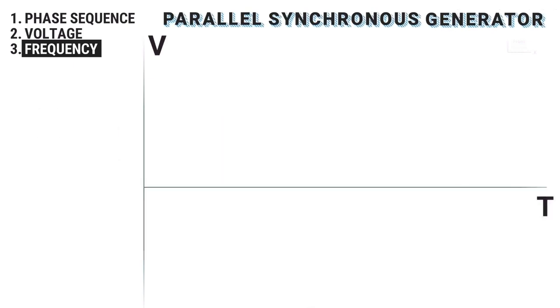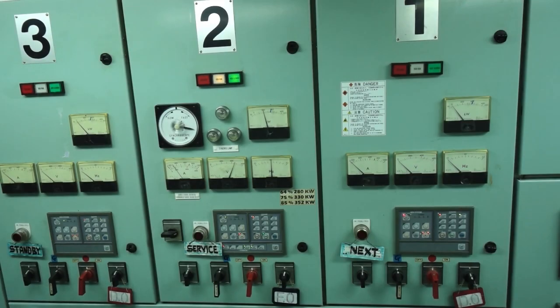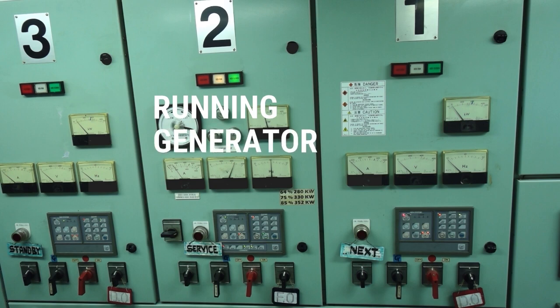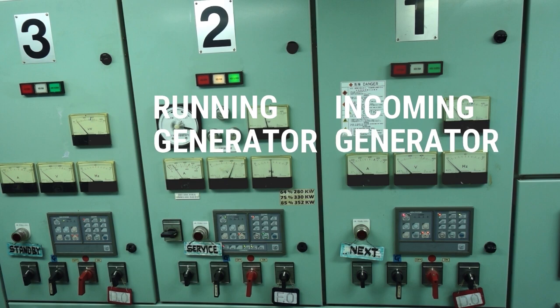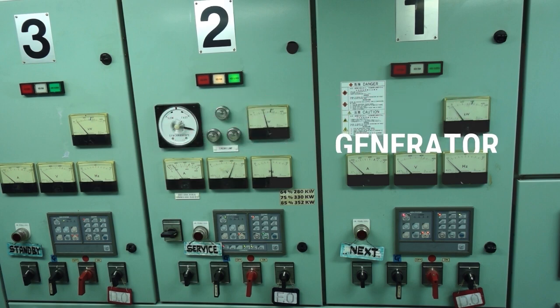Now that we know the basics of paralleling generators, we can start to actually run generators in parallel. You can see that one generator is already connected to the bus bar. This is called the running generator, and the generator that is to be connected to the bus bar is called the incoming generator. I will divide this process of paralleling generators into four steps.